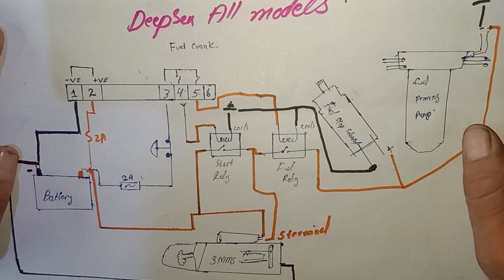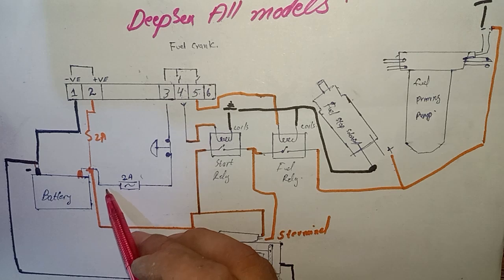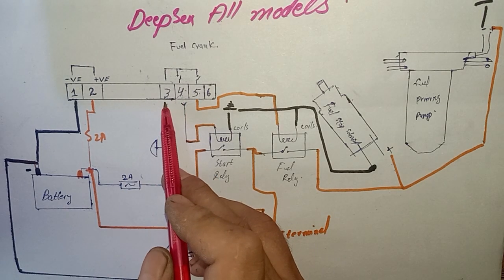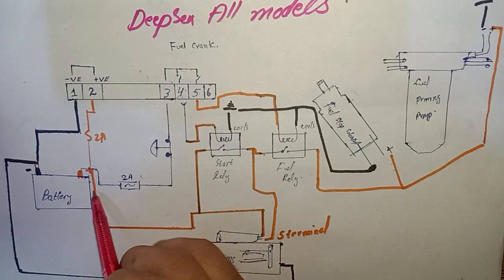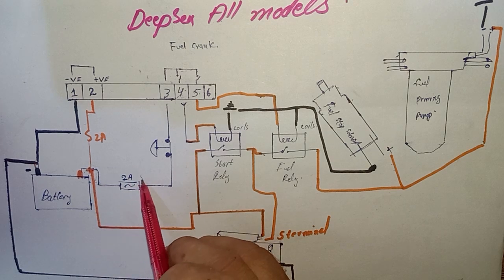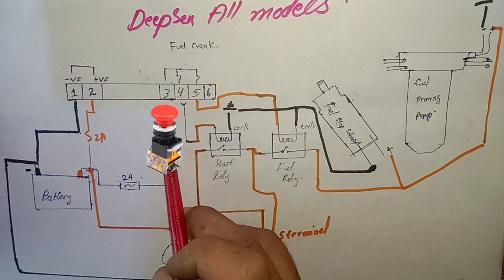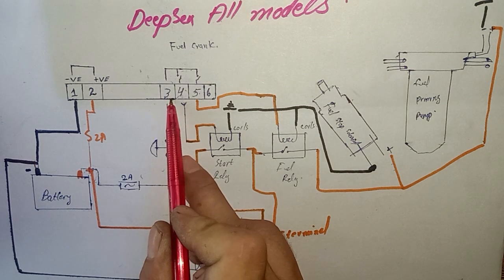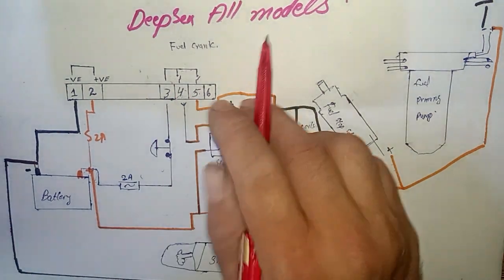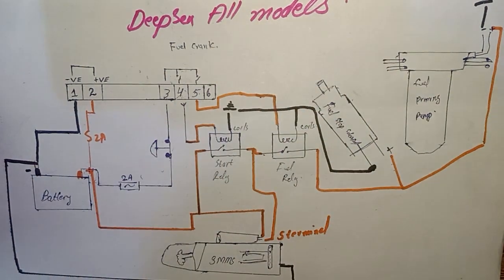Pin number four and pin number five are the output inputs for turning on the fuel and cranking the engine. First of all, we need to give input to the emergency push button pin number three. Battery positive goes out from the fuse, then to the emergency push button NC contact, and then out from the NC and provided to pin number three of the DSE controller. Now this controller is activated and ready to start and work.